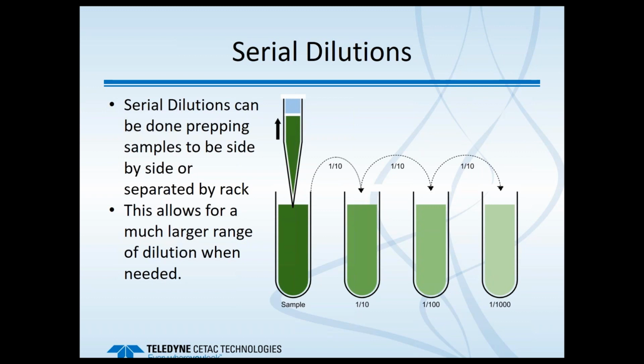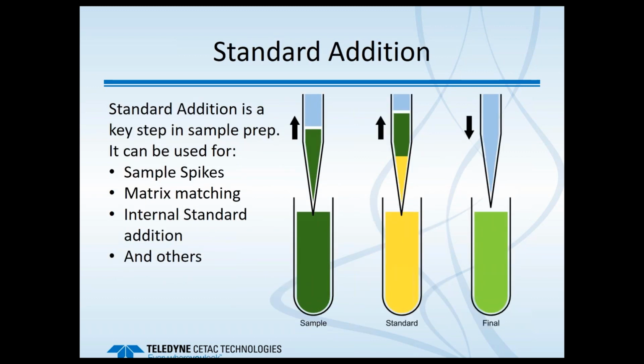And that serial dilution function, of course, provides a much wider dynamic range to the system than it already has. Standard addition is a key step, whether you're doing sample spikes, matrix matching, internal standard addition, what have you. Essentially, it'll pull up an air gap, it'll pull up your sample, it'll pull another air gap to separate the sample from the standard, then it will go into the standard position, pull up your aliquot there, and then dispense it all into the tube.